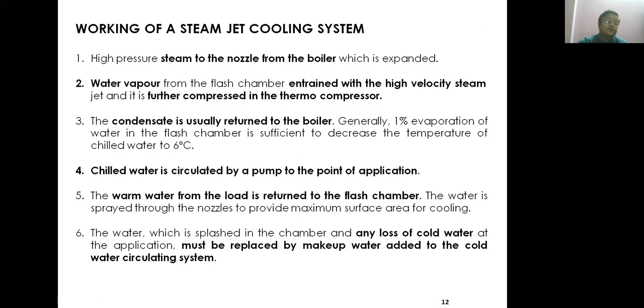Working of the steam jet cooling system. First, high pressure steam goes to the nozzle from the boiler, where it is expanded. This is the main procedure. Water vapor from the flash chamber is entrained with the high velocity steam jet and further compressed in the thermocompressor. The condensate is usually returned to the boiler. Generally, 1% of the evaporation water in the flash chamber is sufficient to decrease the temperature of chilled water to 6 degrees centigrade. Then the chilled water is circulated by a pump to the point of application.